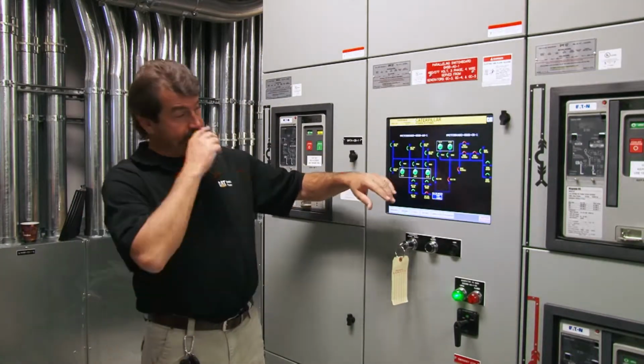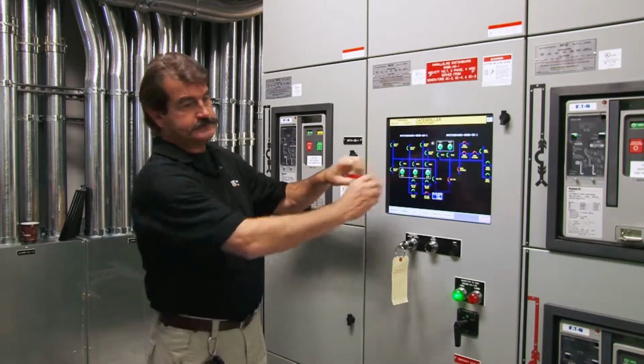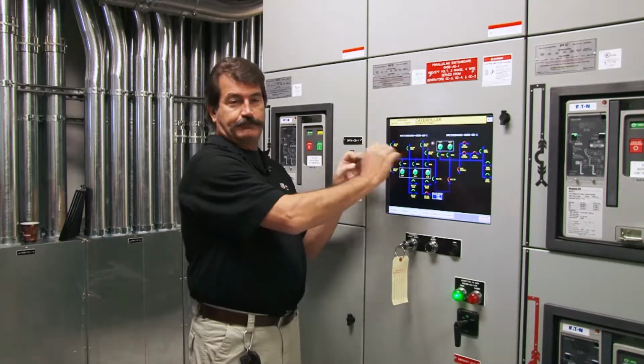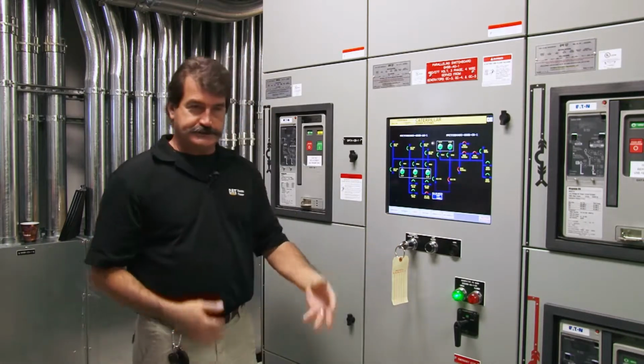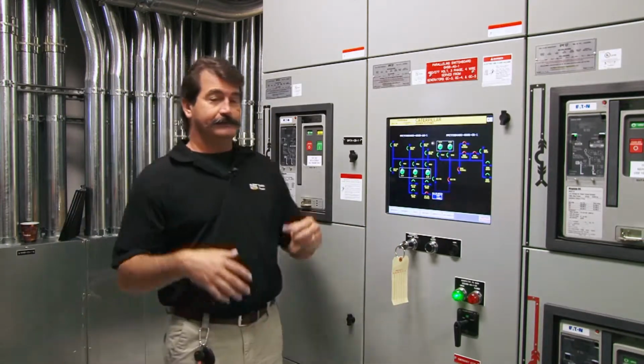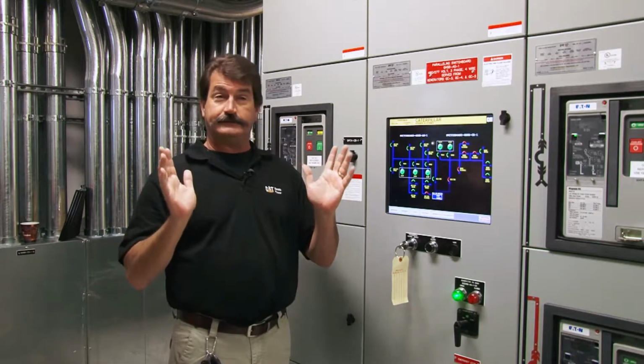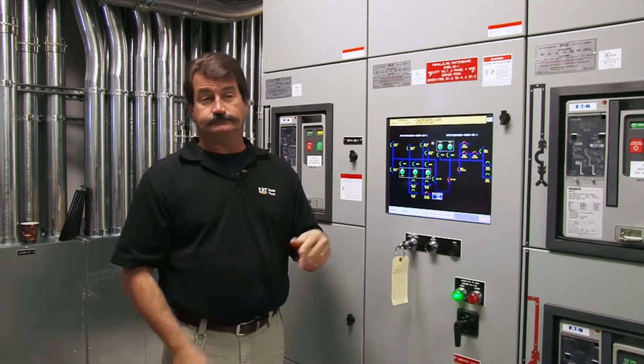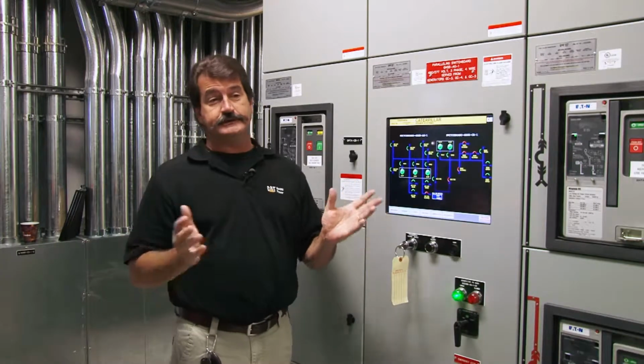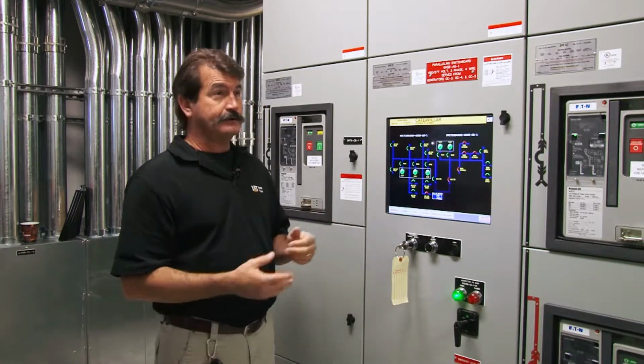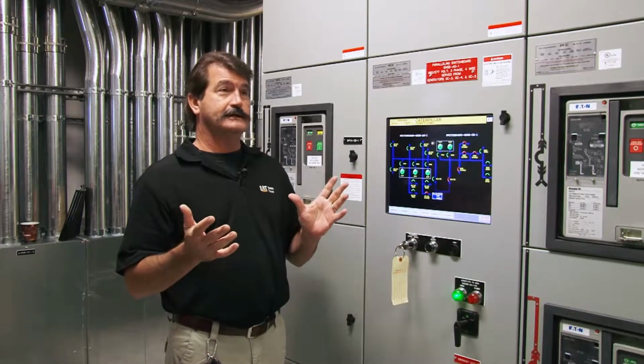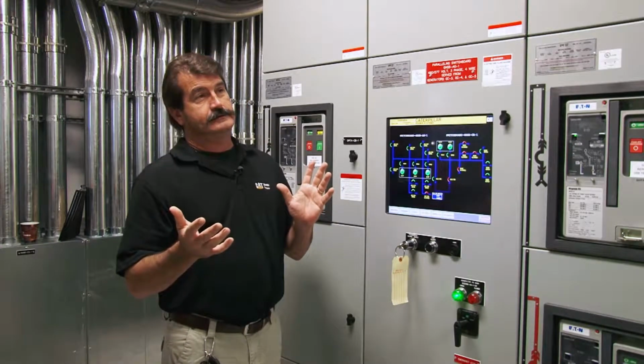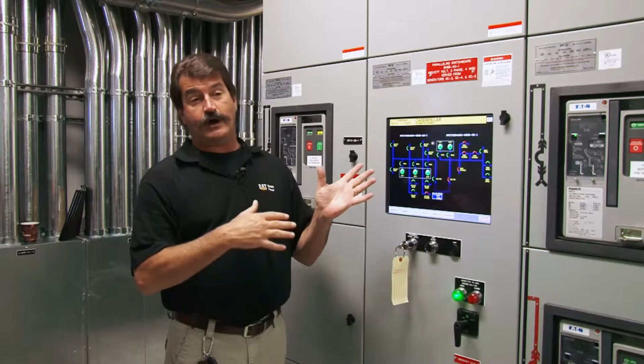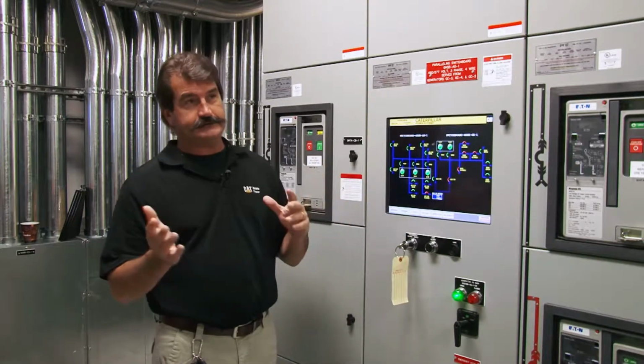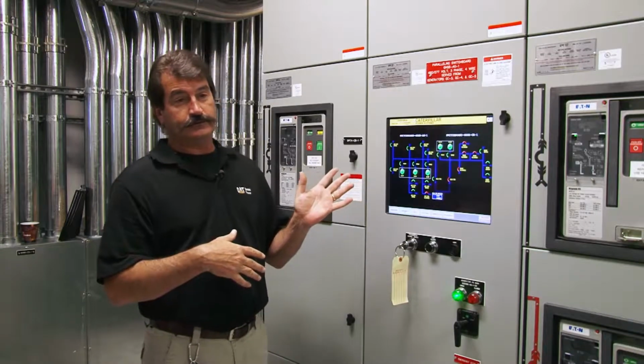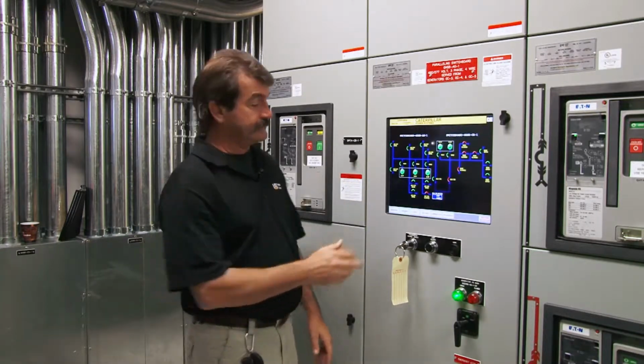Now just to go back over that: you lose power, gens start up, gens come to the bus, breakers close in as the gens come to the bus. Once the breakers are closed in, the ATSs out there swap over, and everything runs until power comes back. Whenever power comes back, the ATSs let us know after they've swapped back over, and once all the ATSs have moved back to normal, we start counting down.